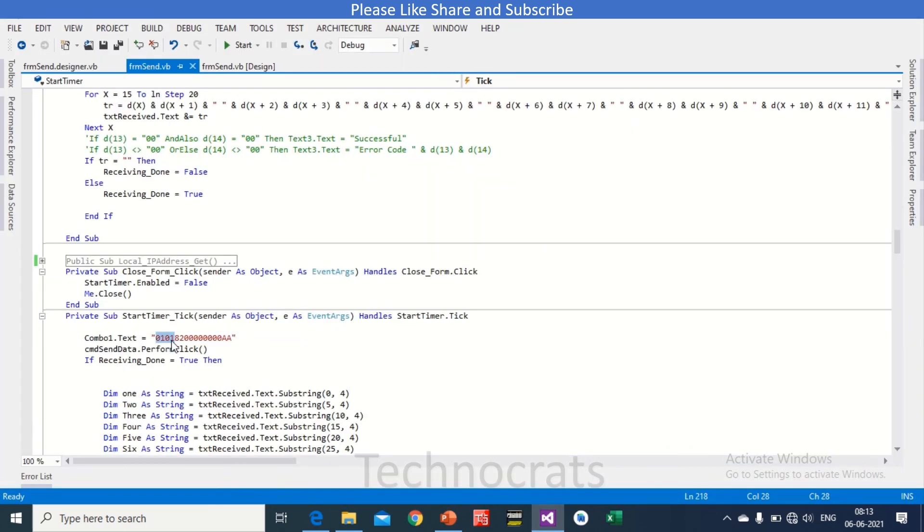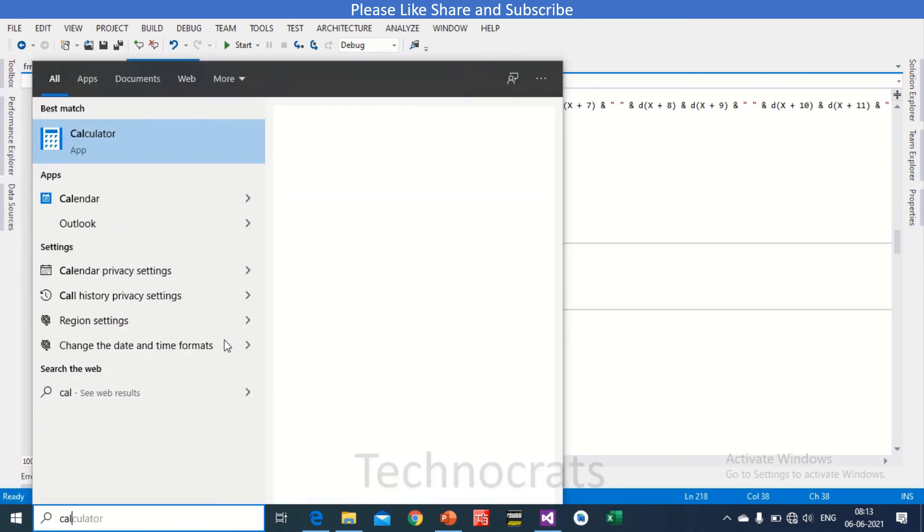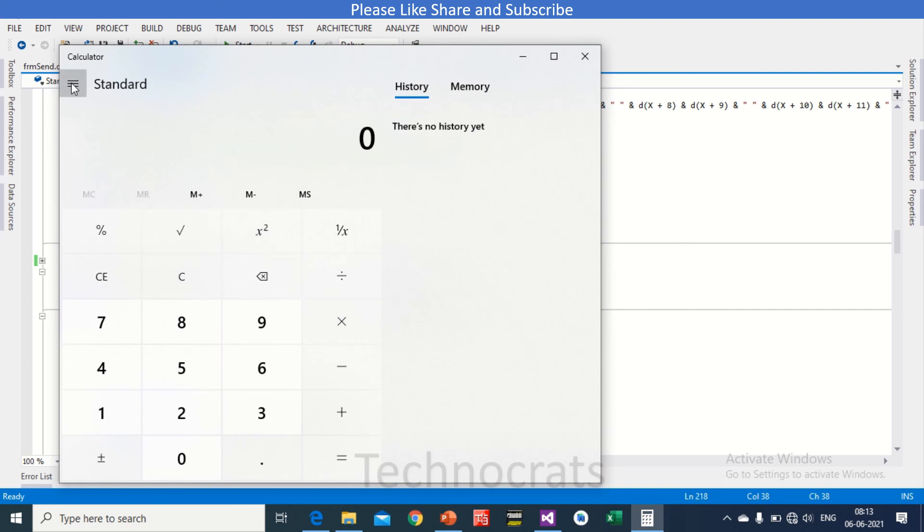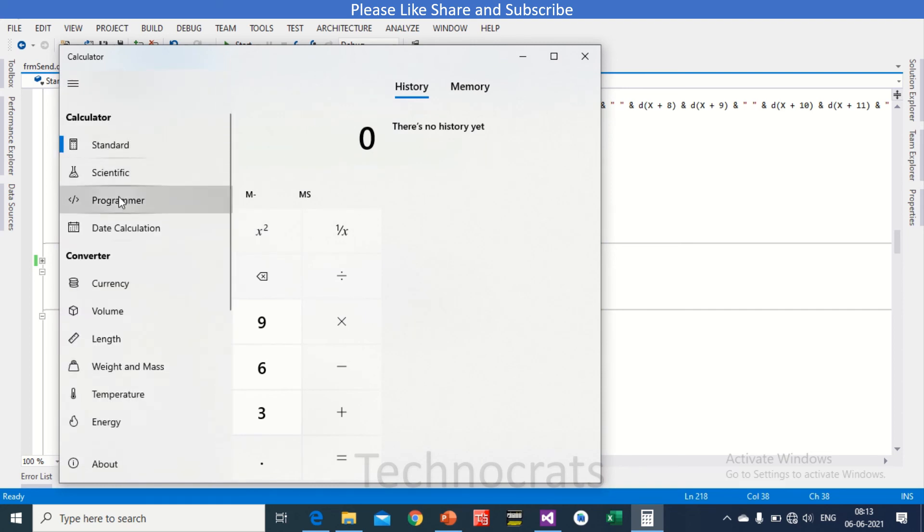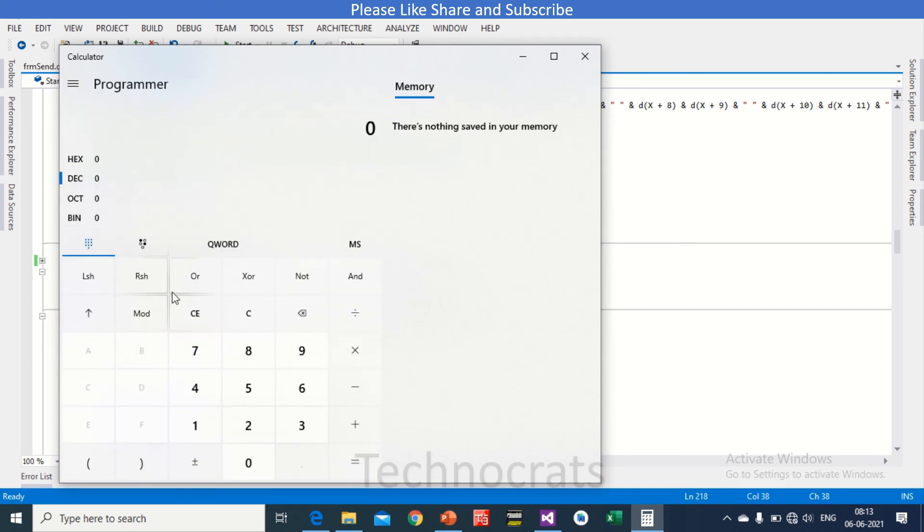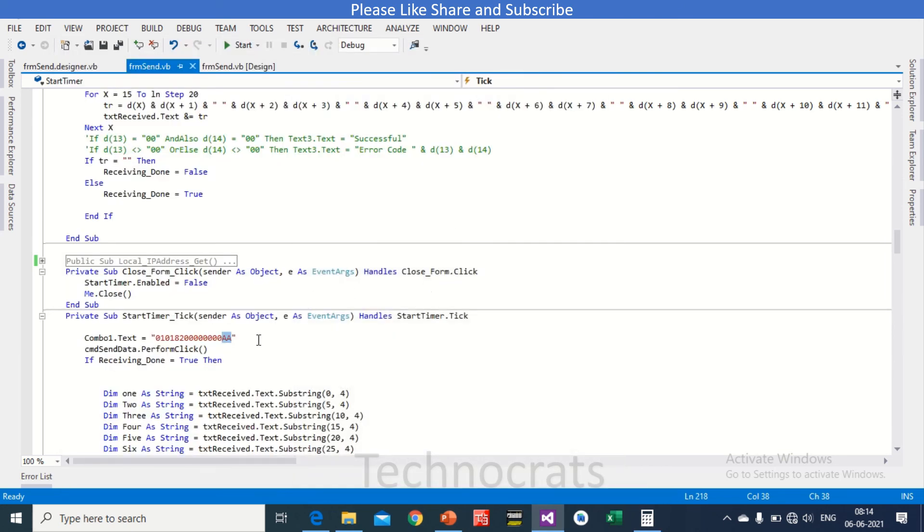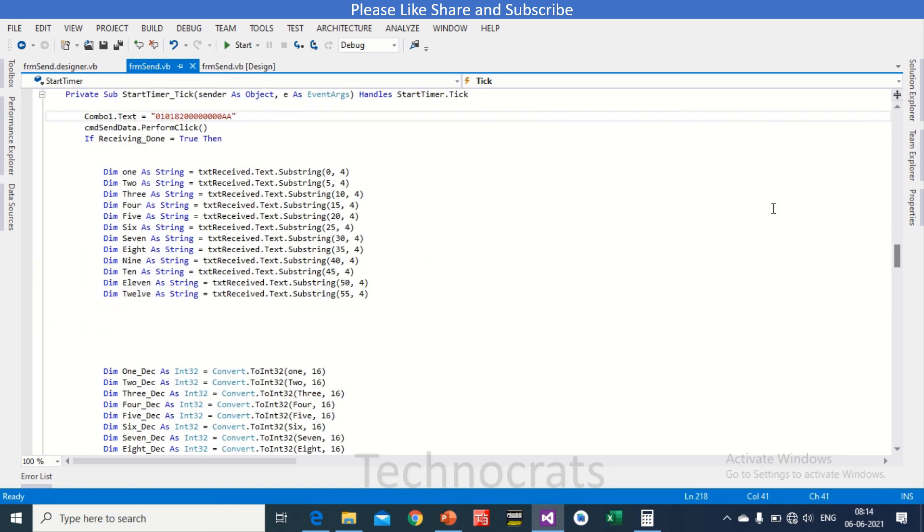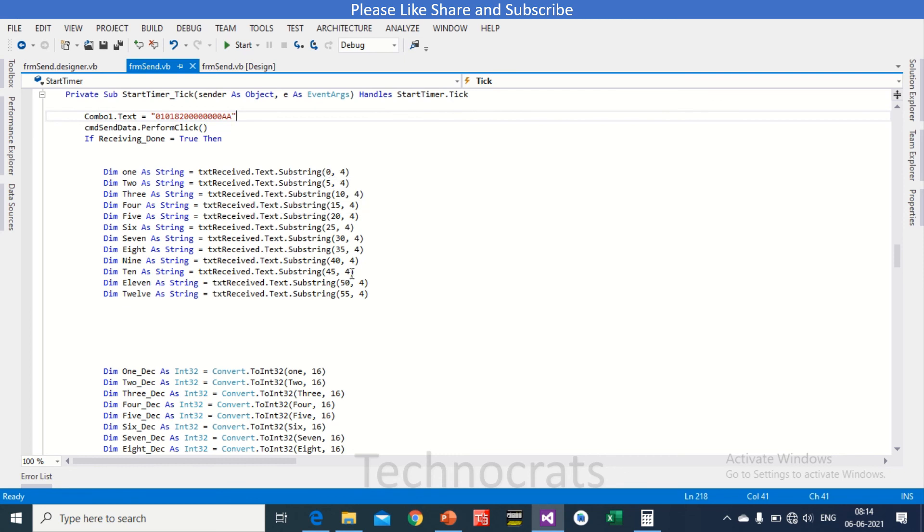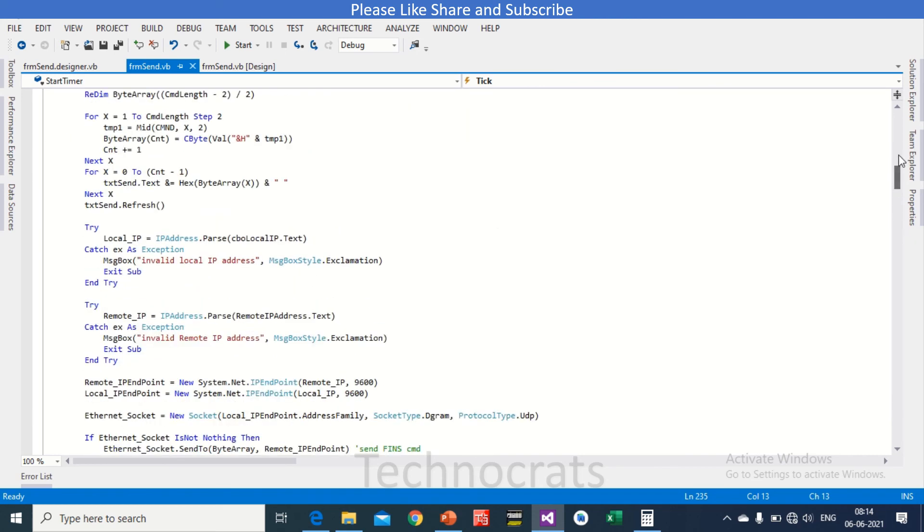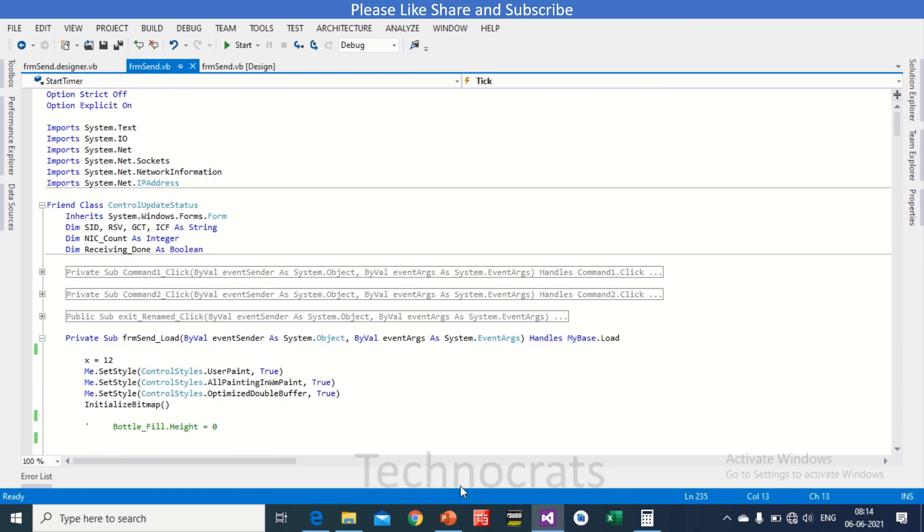0101 82 is for the data register and starting address is 00. Now I have to read total AA, that means if I go to calculator, AA means 170. So I'm total reading 170 data from the PLC, that is from D0 to D169. And I've just converted them in separate string, like the text dot substring 0, 4 until here. So you can use this sample if you want and you can make changes to this. So I have provided this sample in the automation solution blog in a download section so you can download from there.